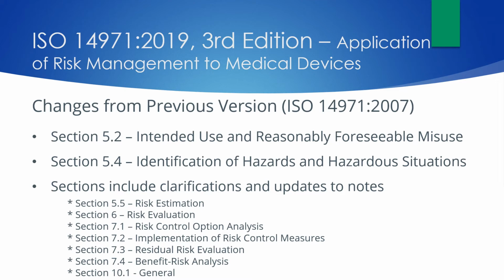Section 5.4, the identification of hazards and hazardous situations, had an addition of a requirement for hazardous situations to be considered and documented. It is now required for manufacturers to address reasonably foreseeable combinations of events that can create hazardous situations. Hazard is defined as a potential source of harm, and some examples can include chemical hazards, electric energy, mechanical energy, thermal hazards, biological hazards, etc. And hazardous situation is defined as a circumstance in which people, property, or the environment are exposed to one or more hazards.